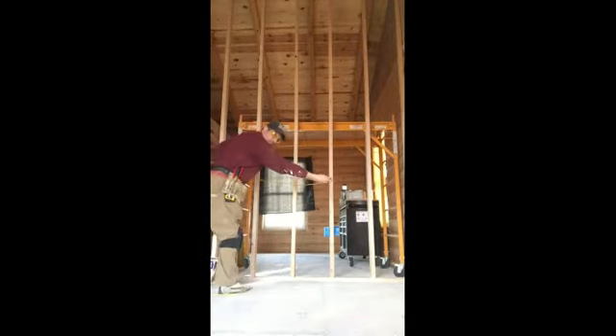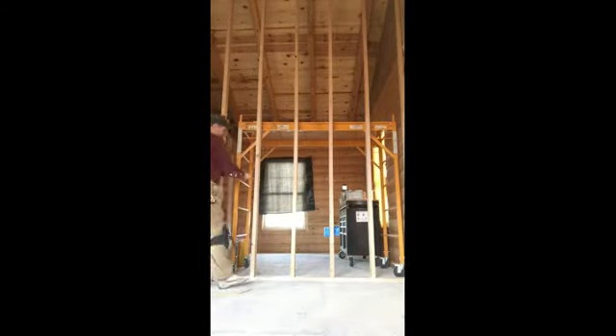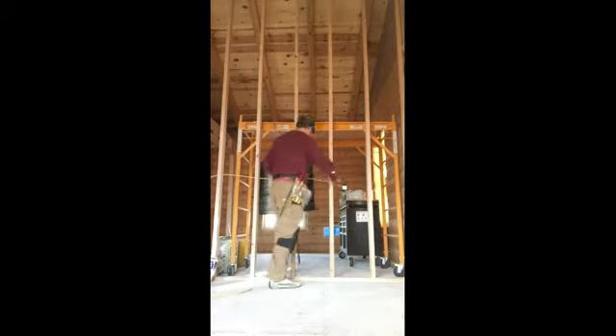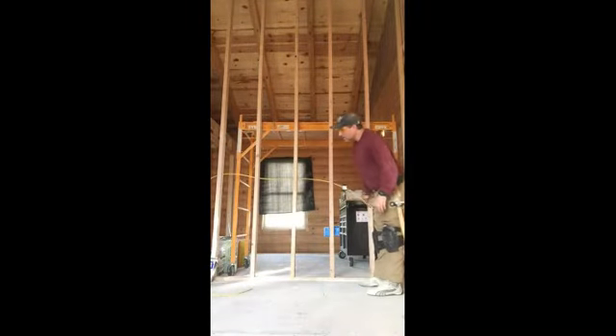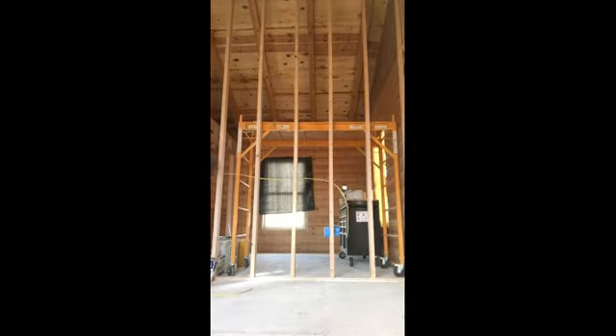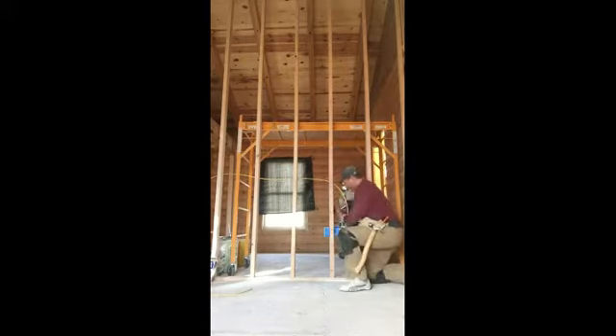So grab your electrical bit and your 1/2 inch wide bit, and then if you need to run 2 or 3 or 4 wires, you might want to use a 1 inch wide drill bit that can make a much wider hole. You're going to drill holes between the studs about 2 feet above every plug box and keep the holes in a straight line.